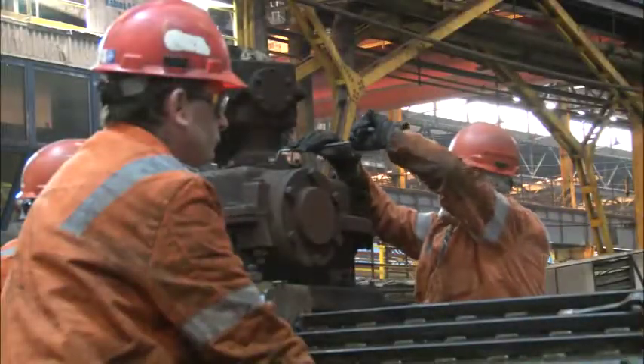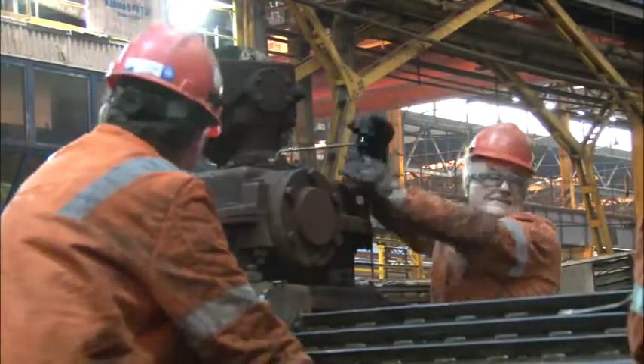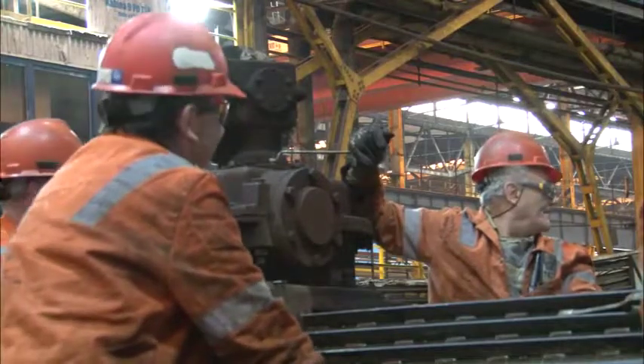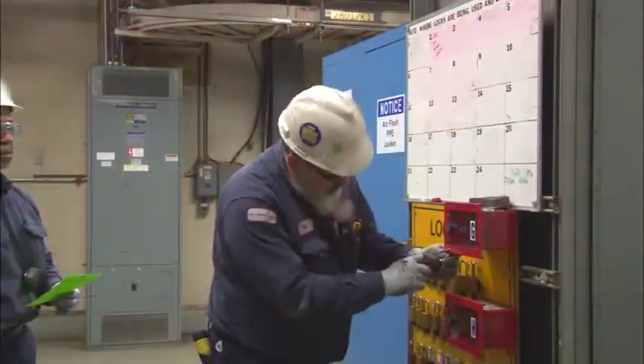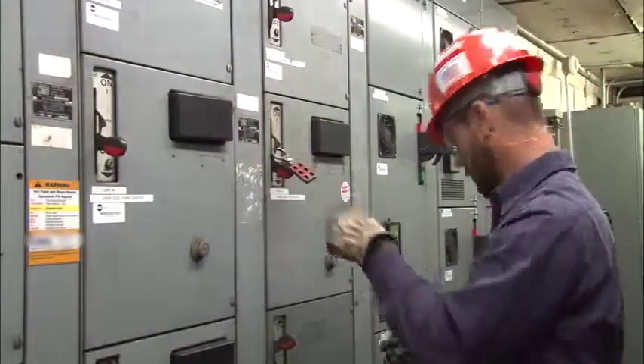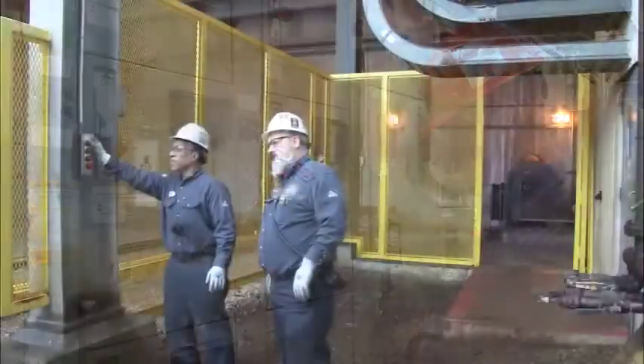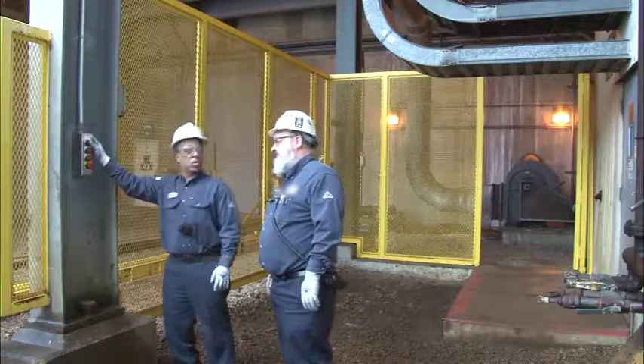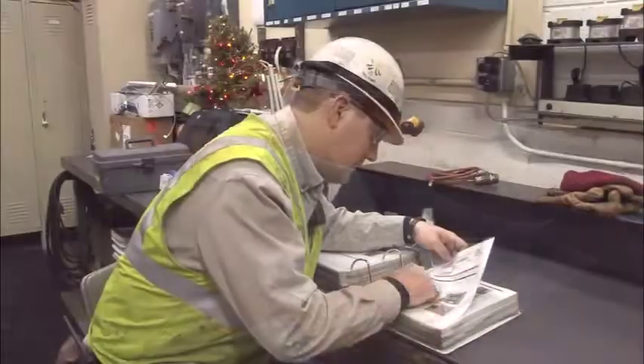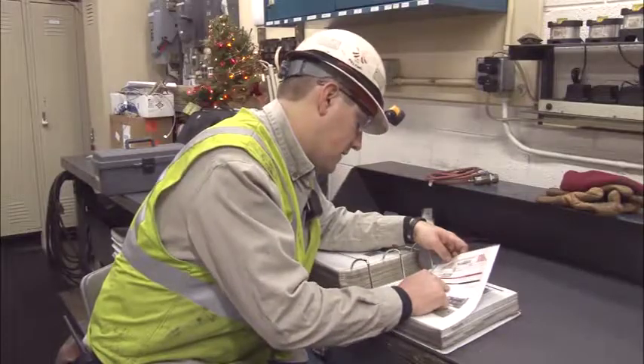Anytime you perform service or maintenance, access the point of operation, or remove or bypass a guard, all energy sources must be locked out. In our business, it is imperative that you lock out 100% of the time and never take a shortcut. It could save your life. This training will outline the important elements of a lockout, tagout, tryout program.